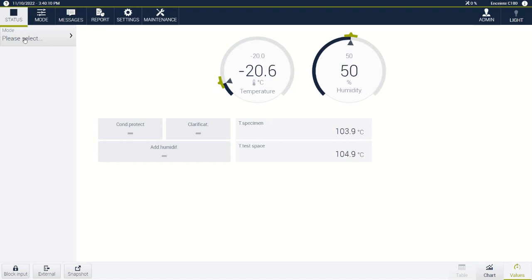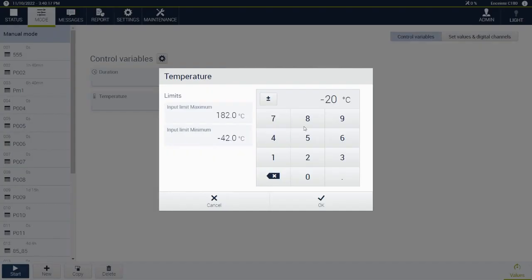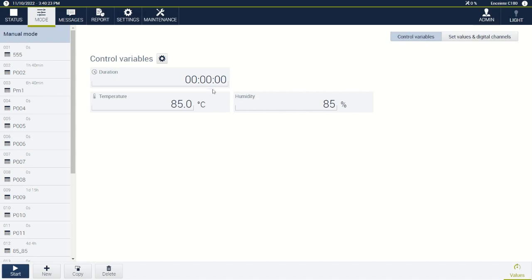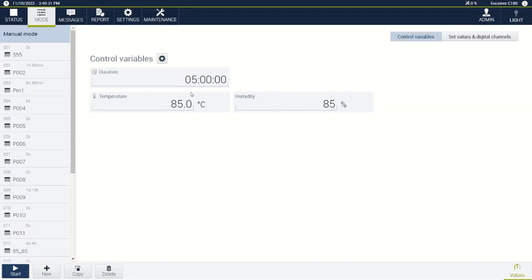So first we're going to click mode and you can see we're already in manual mode. Let's say we want to run at 85°C and 85% relative humidity and we want to run for five hours. Those were all changed just by clicking the variable and changing the number and the units accordingly.